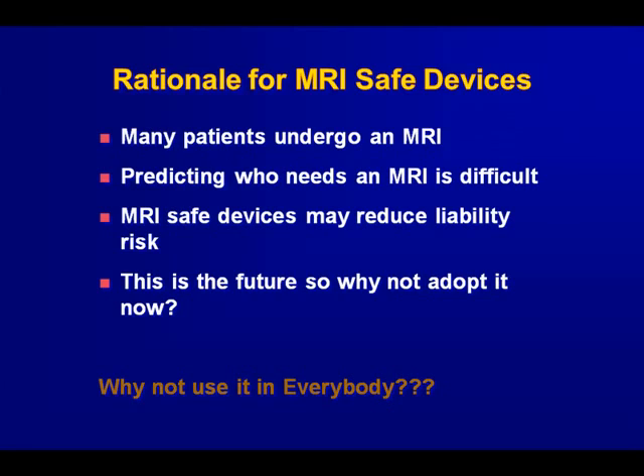Well, let's first start by noting: we don't have MRI-safe pacemakers. We have MRI-conditional pacemakers. The studies have shown that it's safe to be used with a 1.5 Tesla magnet. Many of you probably know there are lots of studies being done now with 3 Tesla magnets and even larger. So there's no idea that any pacemaker is truly safe, and certainly the approved pacemaker is not safe with a larger magnet.